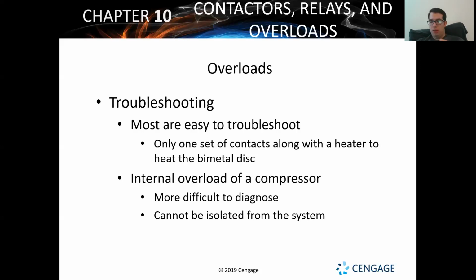So another thing I might look for is a restriction in my suction line. I might look for a lack of refrigerant in my system. These are other things that are going to cause that overheating we see in our compressors for outdoor units, especially for hermetically sealed residential air conditioning systems. That's what we're going to be seeing.